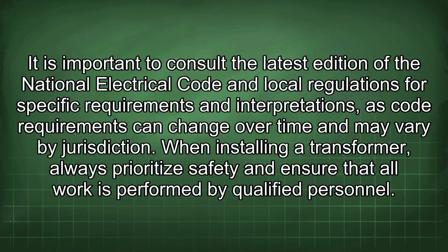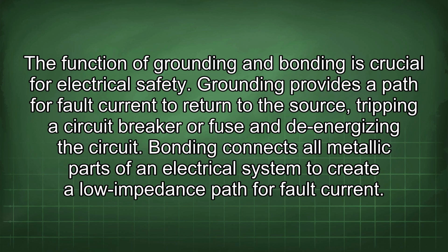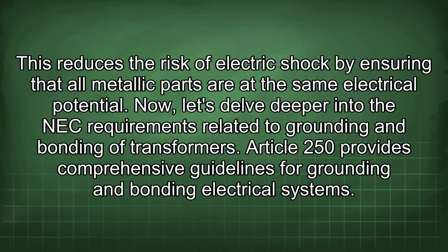It is important to consult the latest edition of the National Electrical Code and local regulations for specific requirements and interpretations, as code requirements can change over time and may vary by jurisdiction. When installing a transformer, always prioritize safety and ensure that all work is performed by qualified personnel. The function of grounding and bonding is crucial for electrical safety. Grounding provides a path for fault current to return to the source, tripping a circuit breaker or fuse and de-energizing the circuit. Bonding connects all metallic parts of an electrical system to create a low impedance path for fault current. This reduces the risk of electric shock by ensuring that all metallic parts are at the same electrical potential.